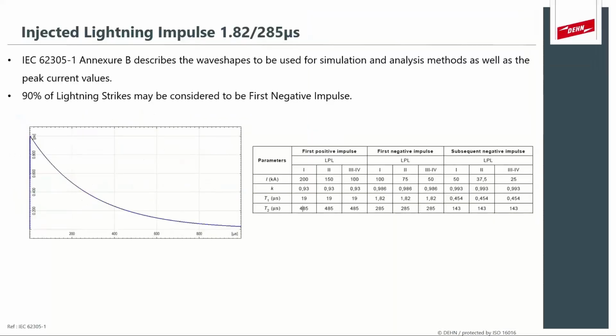As mentioned previously, lightning is an impulse. It's characterized by an impulse wave shape, not a sinusoidal wave shape. We do use sinusoidal wave shapes to represent some ground potential graphs and so on, but in essence, lightning would be an impulse. As I also mentioned in the beginning, 90% of lightning strikes may be considered to be first negative impulse. And that's from IEC 62305, which is the main lightning protection standard across the world.